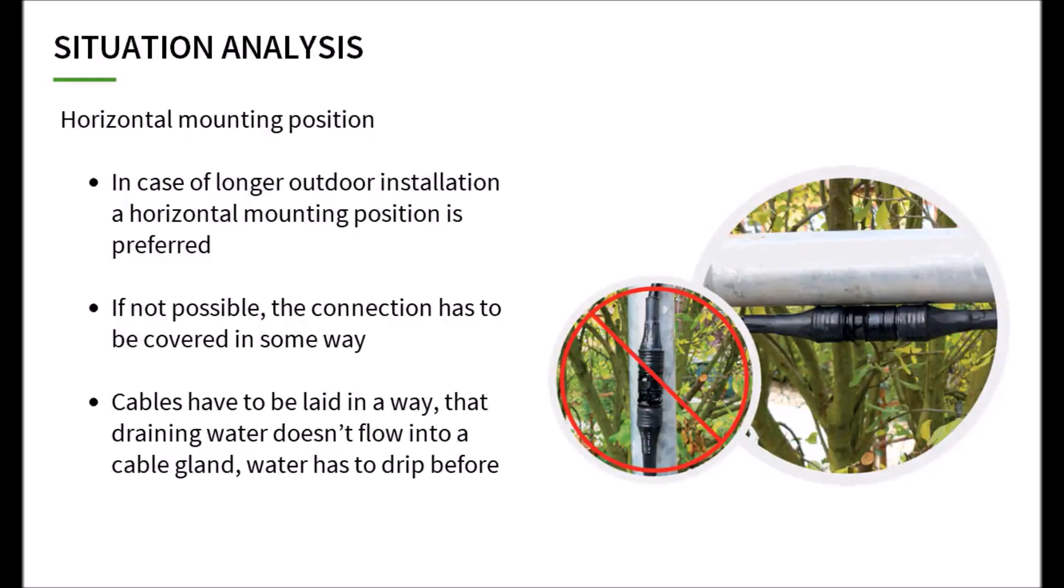Horizontal mounting position. If the unit is to be used outdoors for a longer period of time, a horizontal installation position must be selected to ensure that the water can drain away. If this is not possible, an additional cover should be used for protection. The cable routing also plays an important role. The cable must be laid in such a way that the water draining off it is not led to the cable gland but drips off beforehand.